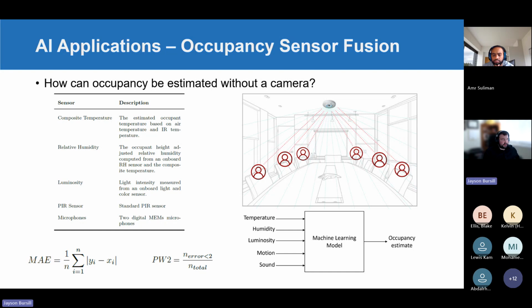Now, in terms of evaluating the validity of the model, mean absolute error was one of the metrics, but also a metric that we called persons within 2, which is the amount of time through all the samples that the error was less than 2, which we kind of sorted out from looking at different spaces and meeting room occupancies that this was an acceptable level, right? Because you could do 0 to 1 really easy because of the PIR sensor - people are actually in the room or not in the room, like 99.9% of the time. But then once you get above 2, that's where it starts to get interesting.